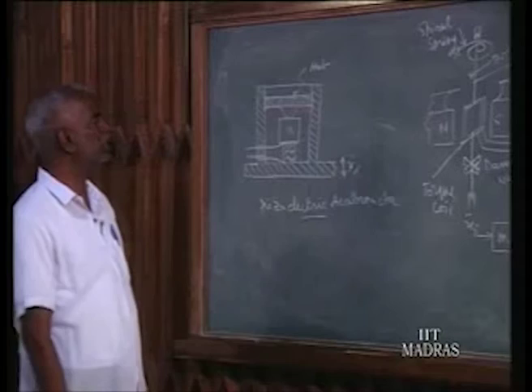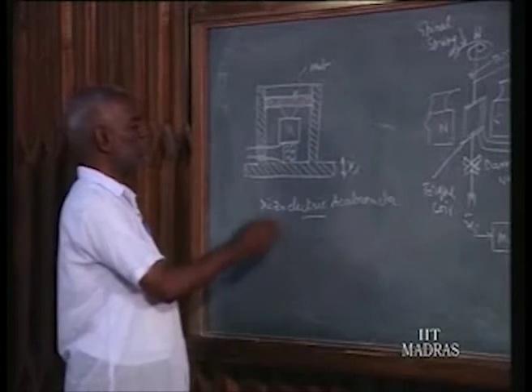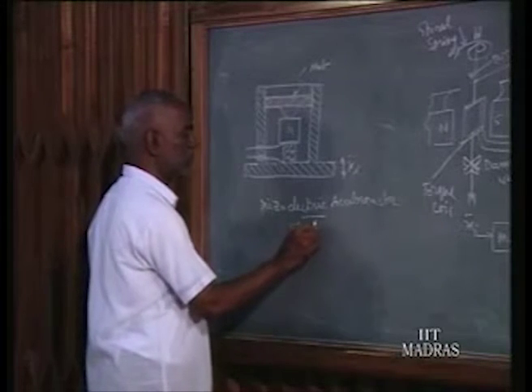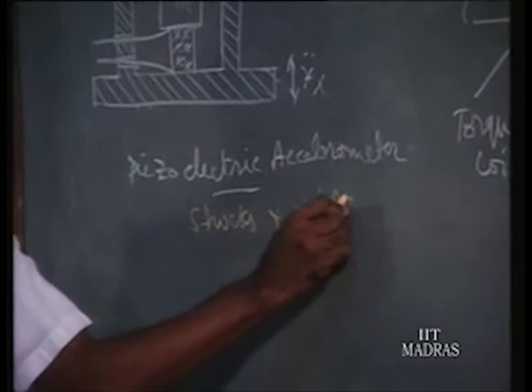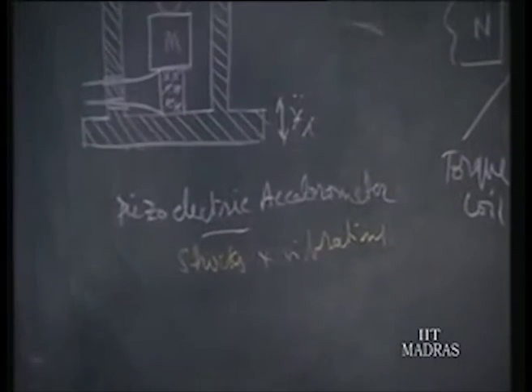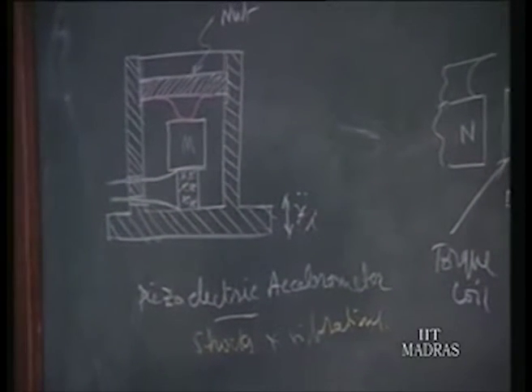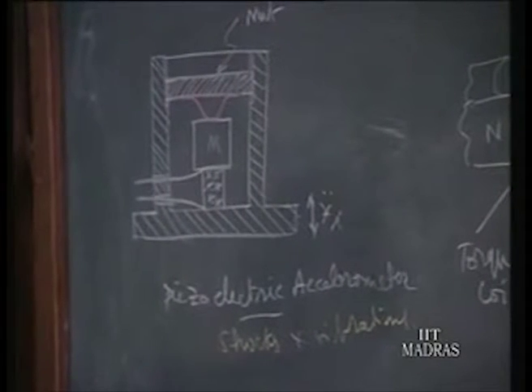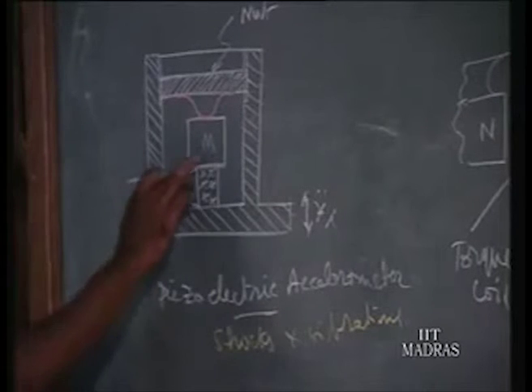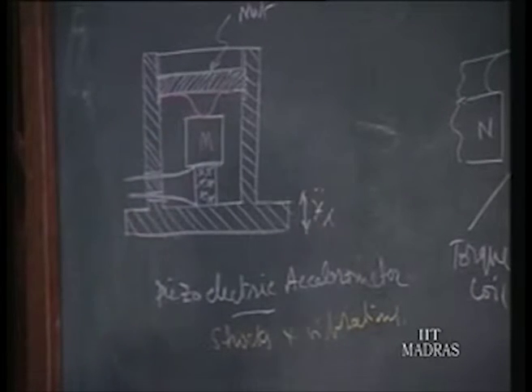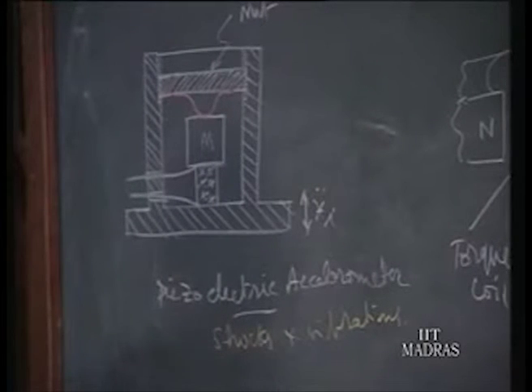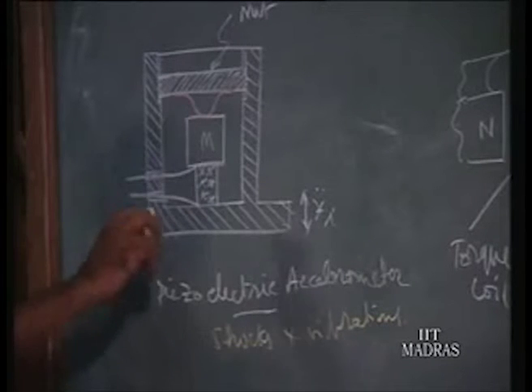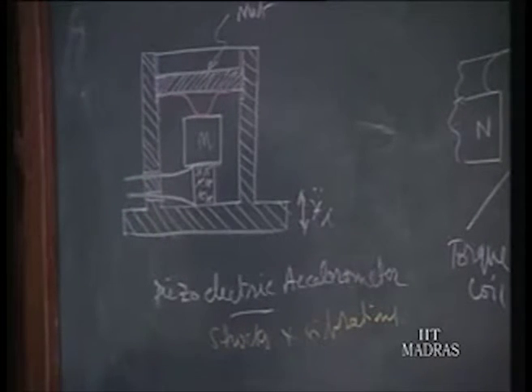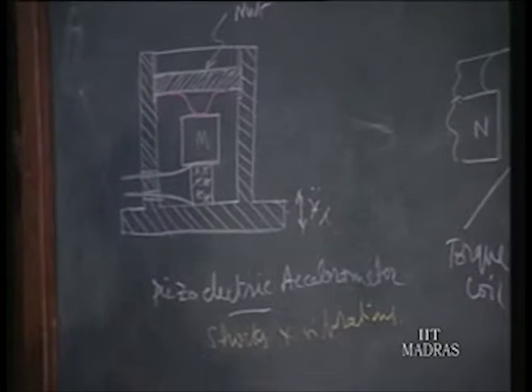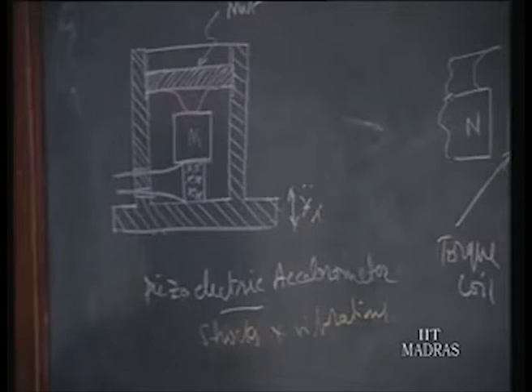The next type of accelerometer is the piezoelectric accelerometer. It is very widely used in measuring shocks and vibrations, because it has a very high undamped natural frequency. Here the same mass is there. For the relative measurement of the mass, the earlier types used potentiometer, LVDT and the reluctance principle. Here we use piezoelectric crystals, say a quartz crystal, to measure the relative motion of the mass with reference to the frame of the seismic pickup.